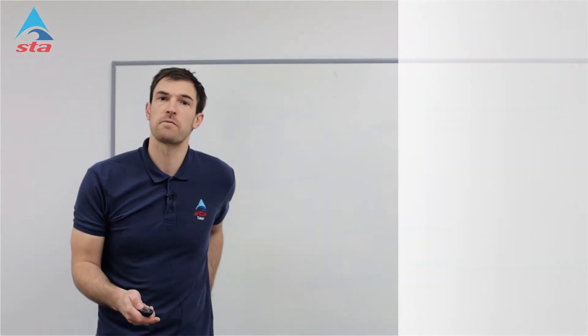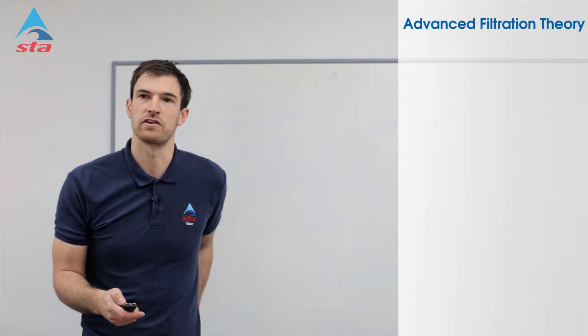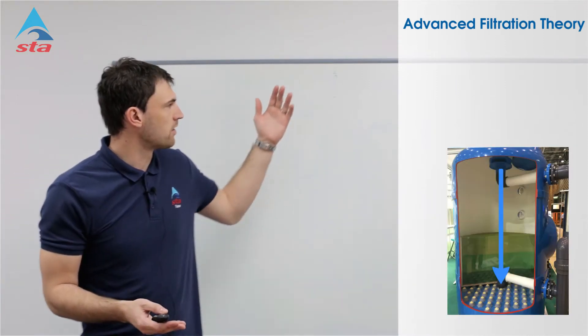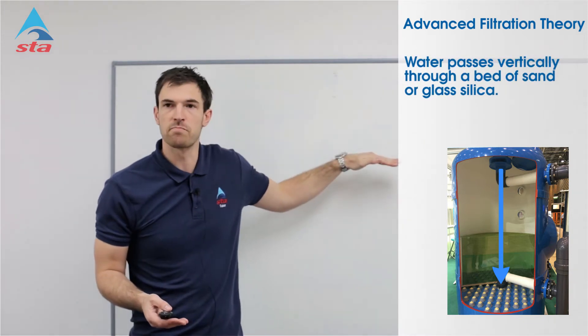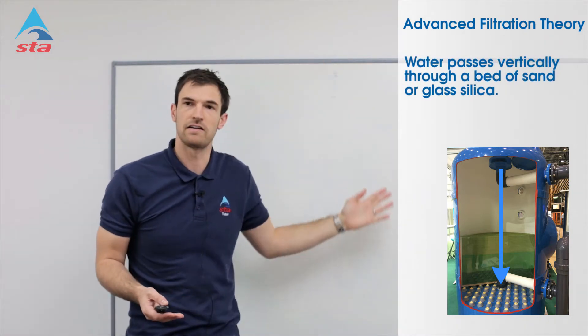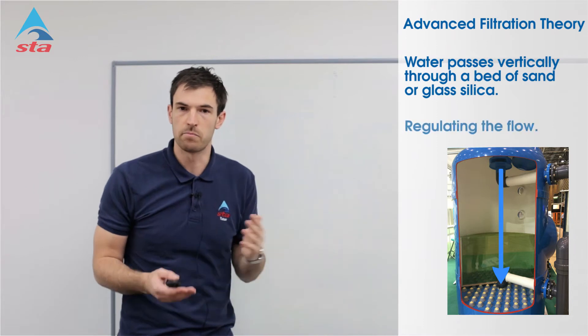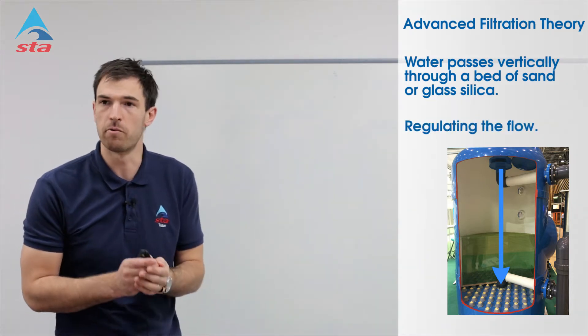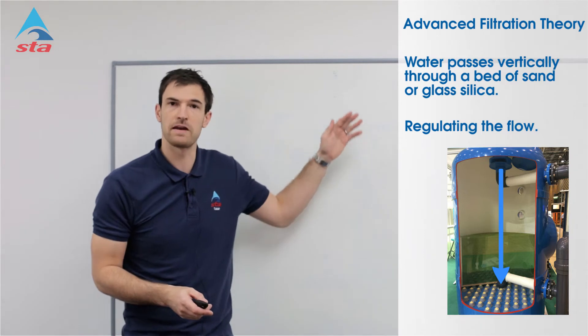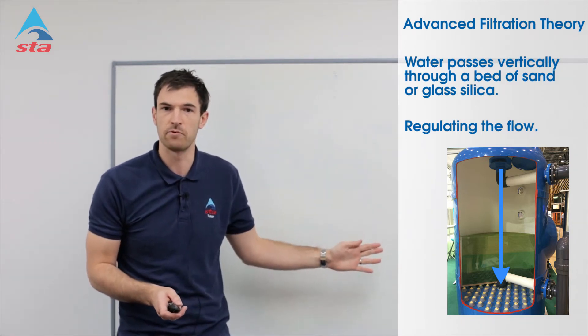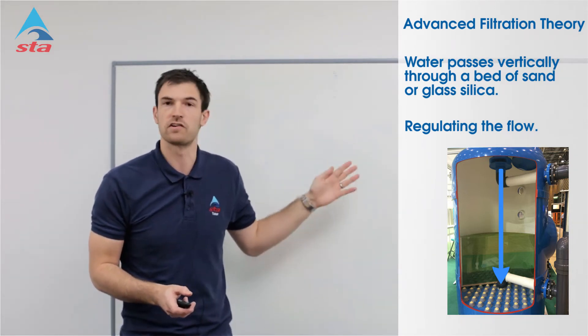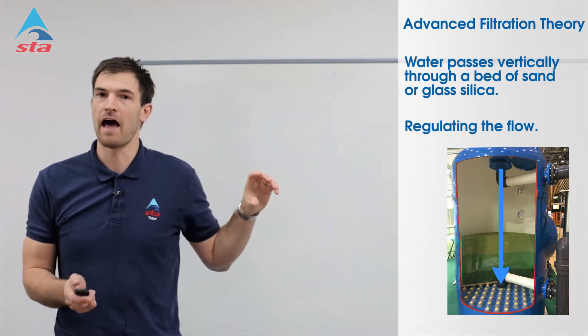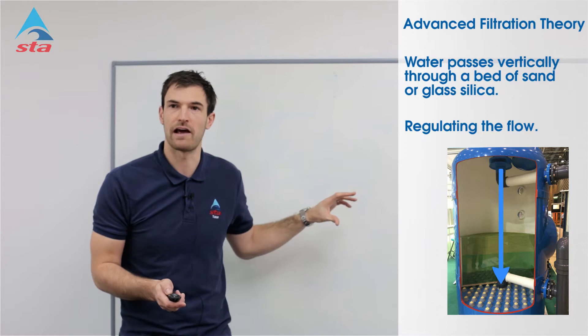The first thing we need to look through is the basic principles of filtration. With your filtration system you've got your sand bed, a minimum of 800mm, and your water passing vertically down through that sand bed. It's important to remember that regulating the flow is one of the most important elements. The slower the speed through that sand vertically downwards, the better and more efficient the filtration is going to be. We're going to take an in-depth look at that speed and how we calculate it.